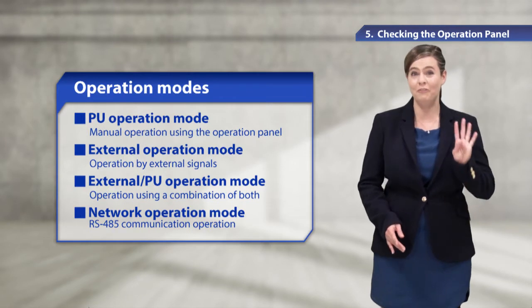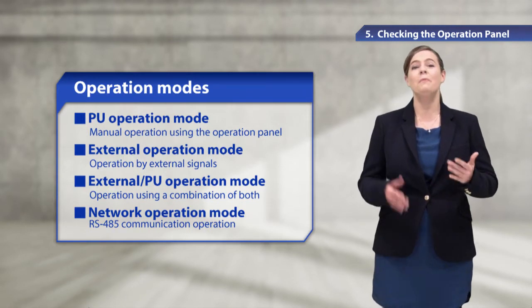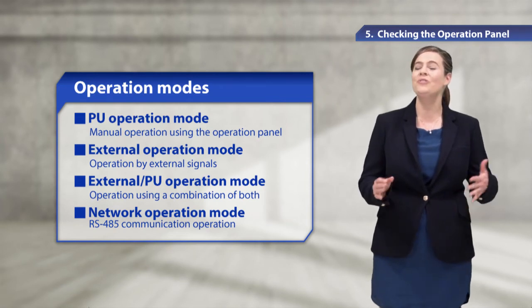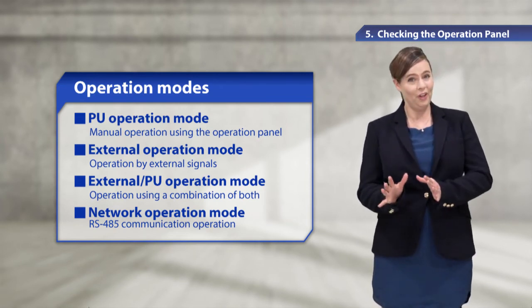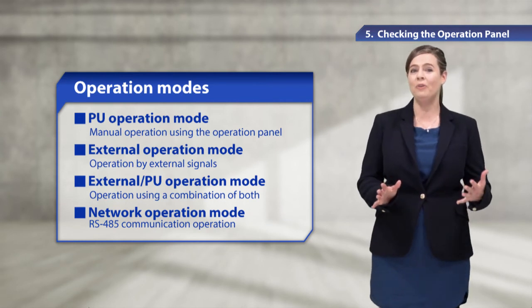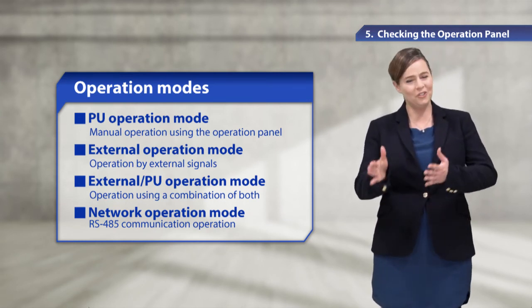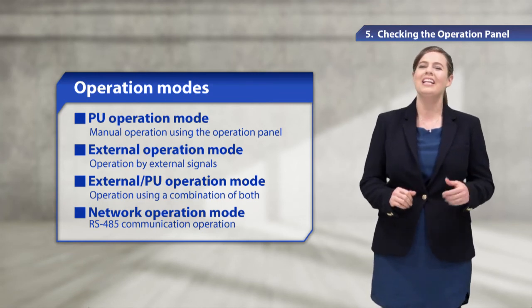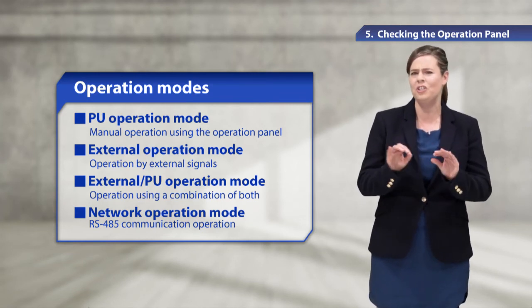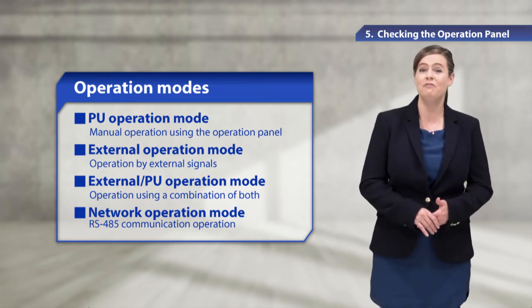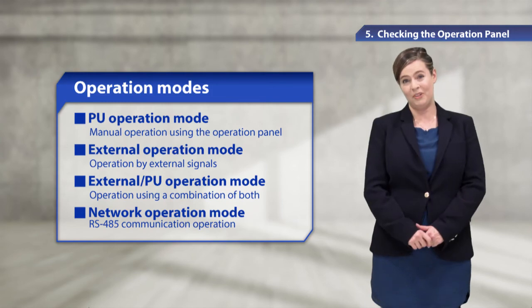The inverter has four operation modes. The PU operation mode is for manual operation using the operation panel. The external operation mode is for operation by using external signals. The external PU operation mode is for operation using a combination of both. And the network operation mode is for RS-485 communication operation.